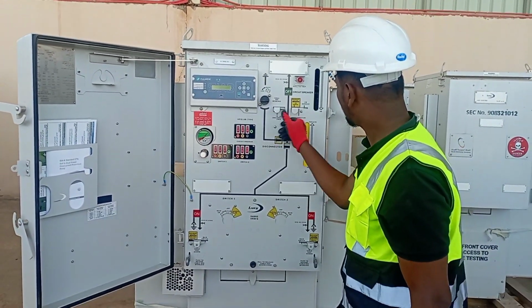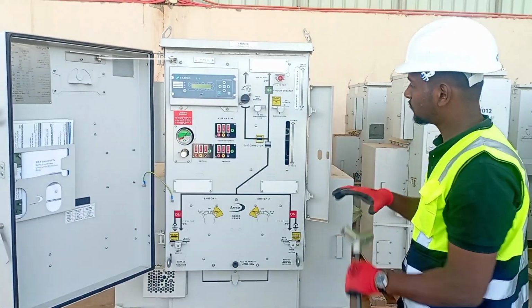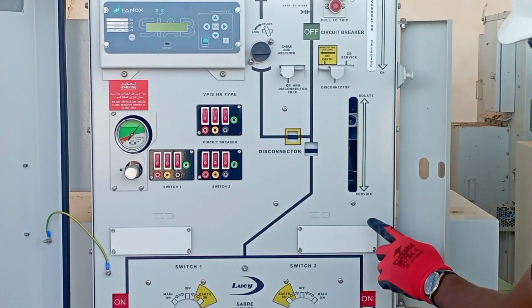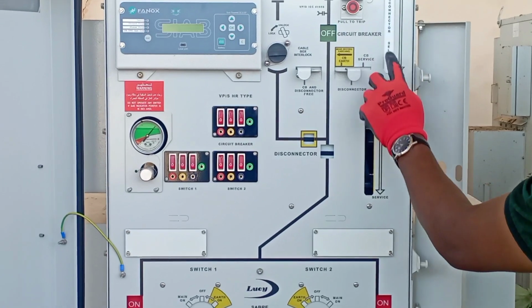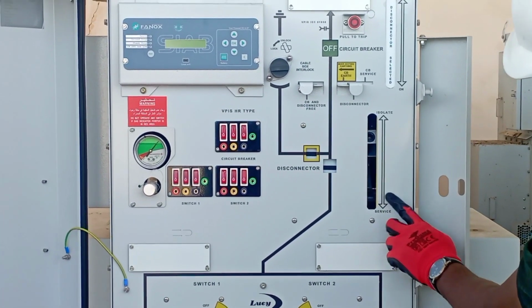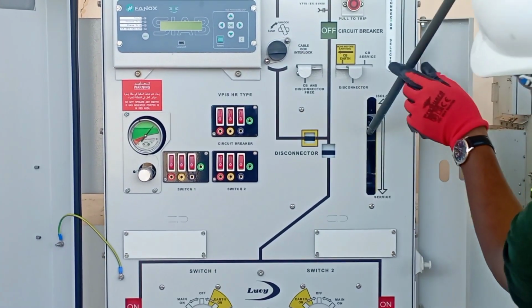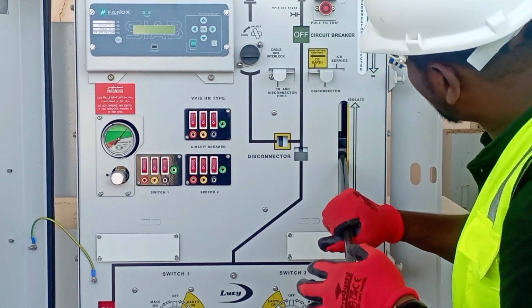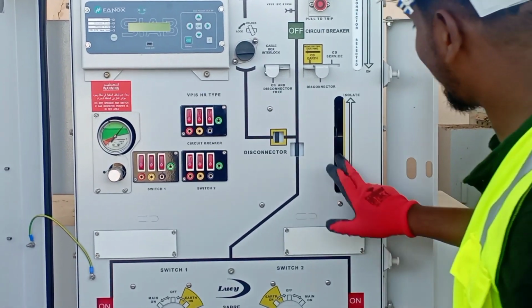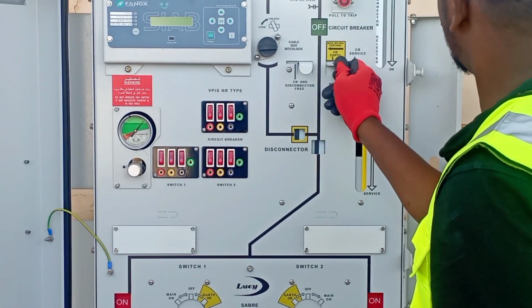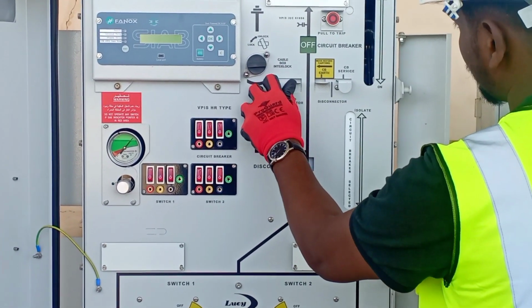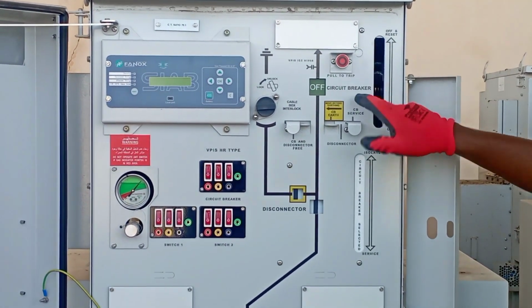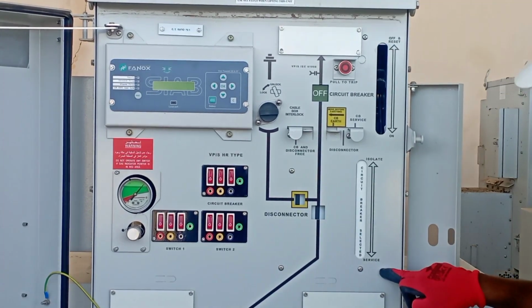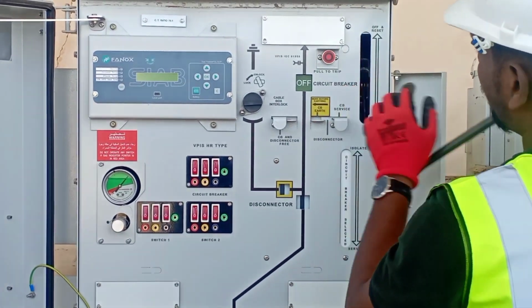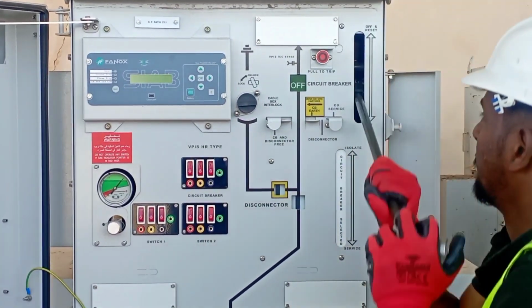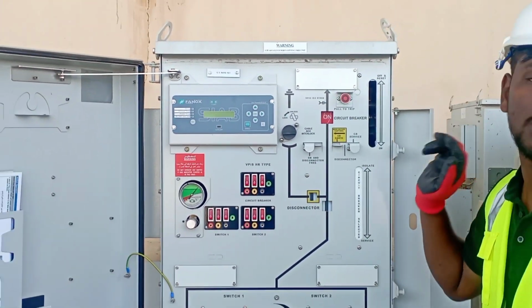Okay. And now we have to operate disconnector switch. Now this one in isolate condition, we have to put in service condition. After that, we need to open this one and put it on condition. Okay, now we are making this disconnector switch from isolating point to service point. We have to use little power for making this one. So now we are going to on this circuit breaker again. Once we put the disconnector switch on service condition, we have to make it on circuit breaker. So by using this another end of this handle, we can pull. So the T off is in on condition.